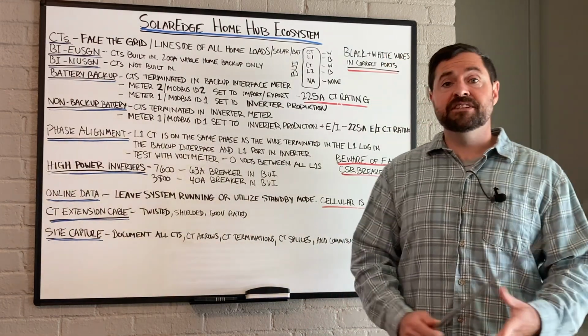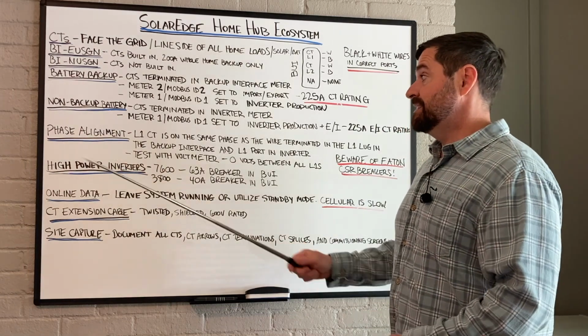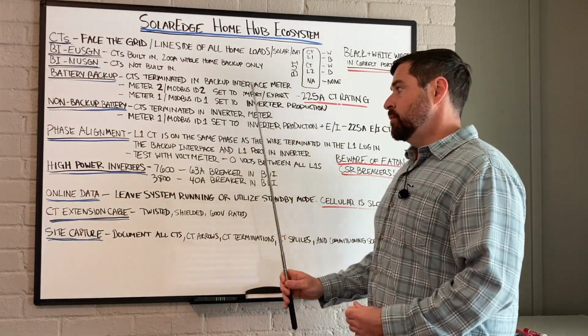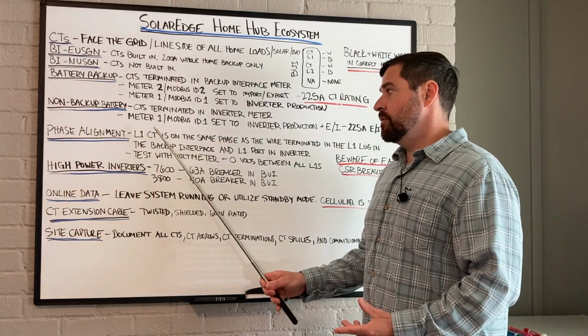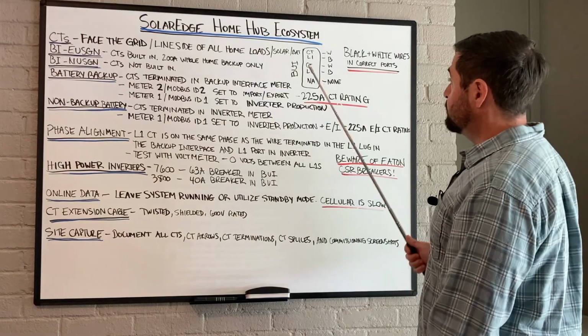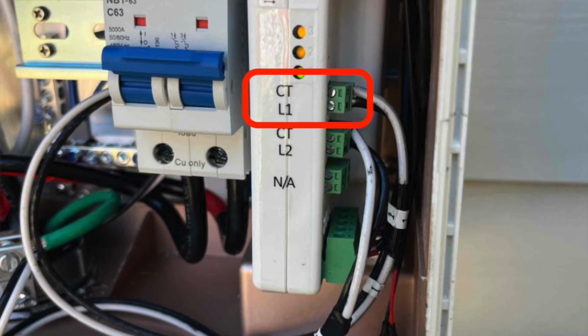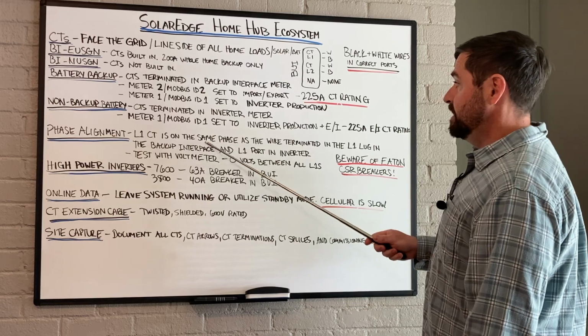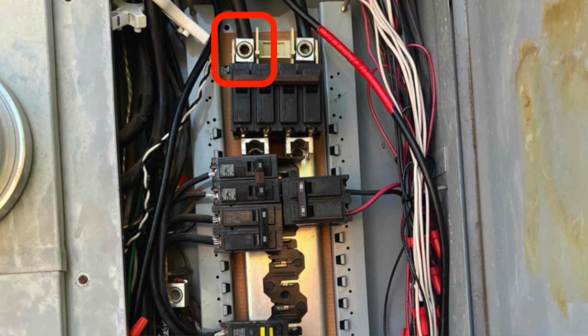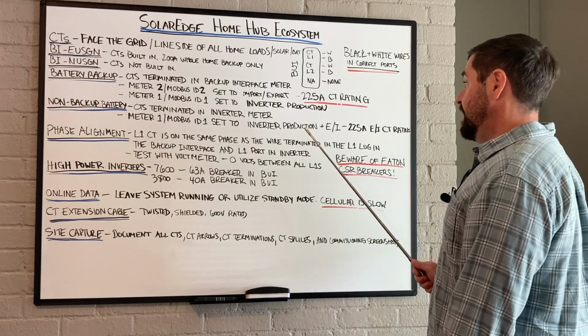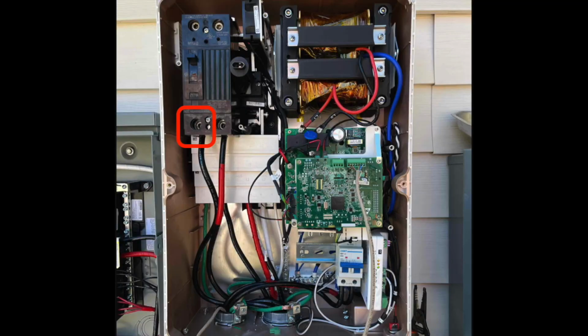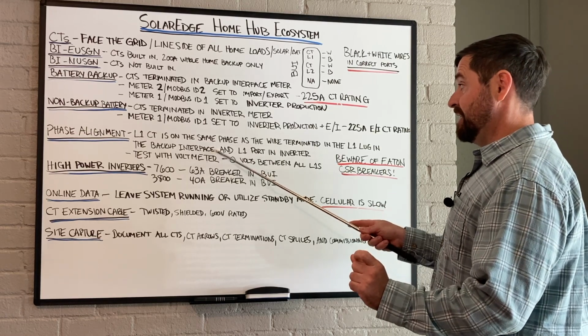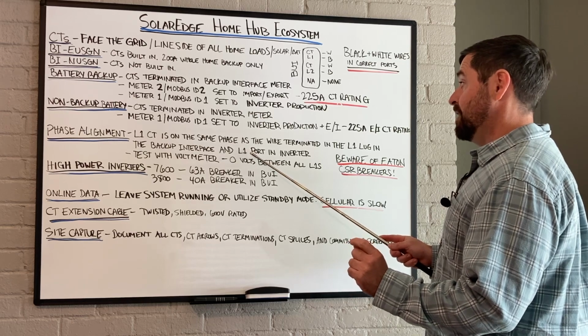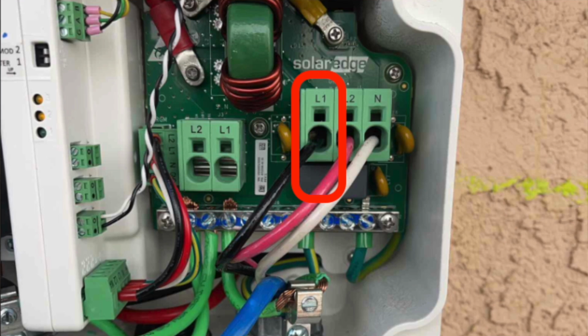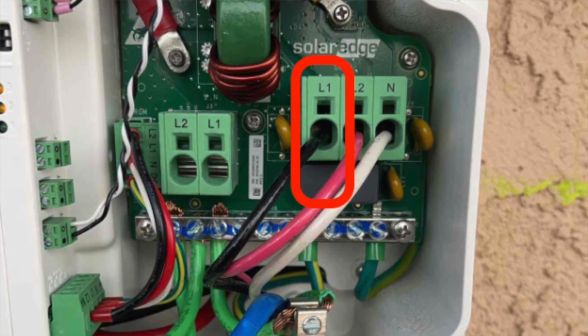The next most common reason for CT failures is phase alignment. Essentially, what we need to do is make sure the CT that is terminated into the L1 CT port in the energy meter is on the same phase, or the same wire essentially down the line, as the wire that's terminated in the L1 lug in the backup interface. Now that also has to be on the same phase as the wire terminated in the L1 port on the solar inverter. So again, you just have to use colored wire.